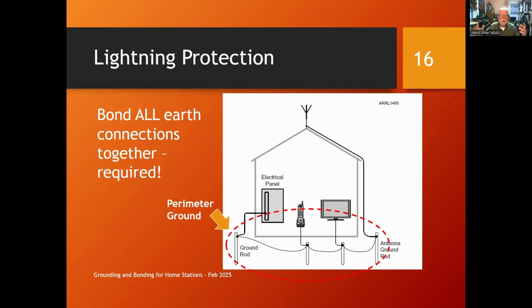And what happens then? Well, that's when you hear stories like, I was sitting there minding my own business and there was a lightning flash outside and a big green arc went from my home entertainment system to my telephone, and now nothing in the house works anymore. That's because the ground systems were not going up and down together. One ground system went much higher than the other. It may have actually equalized after a while, but for a long enough period of time, there was 10,000 volts between them and destructive voltage differences in currents. So you beat that by running a big heavy wire.